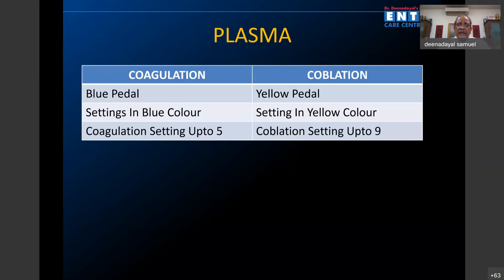There is a blue pedal and a yellow pedal in Coblation. The blue pedal is always to coagulate and the yellow pedal is always to ablate. The blue one has a maximum setting of five.